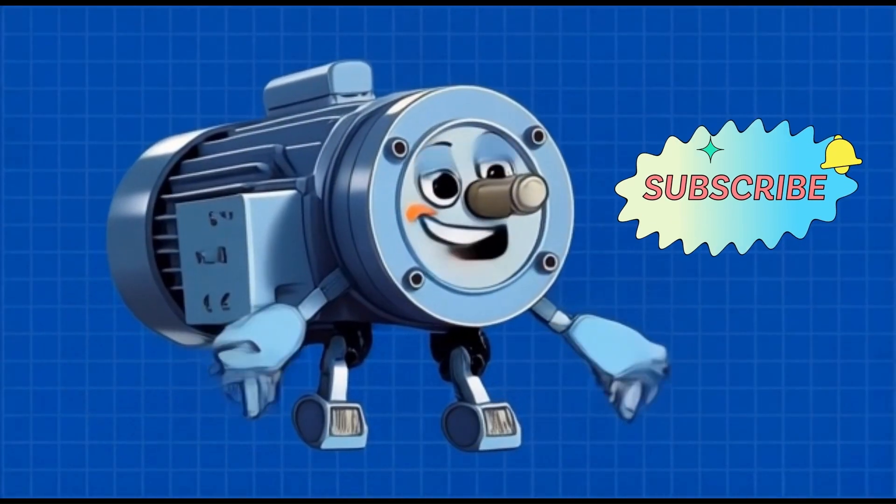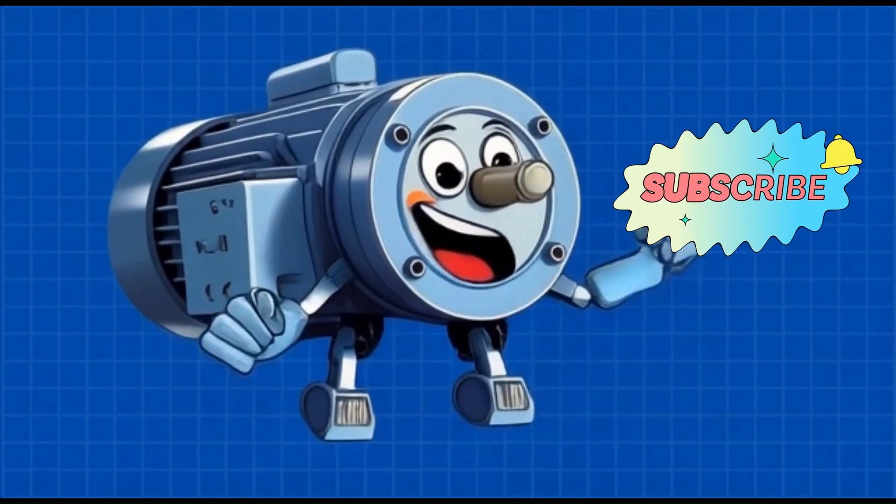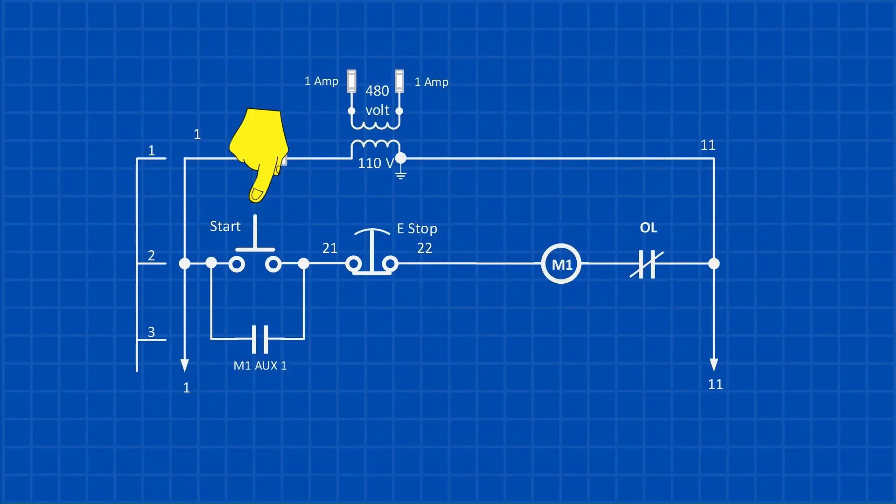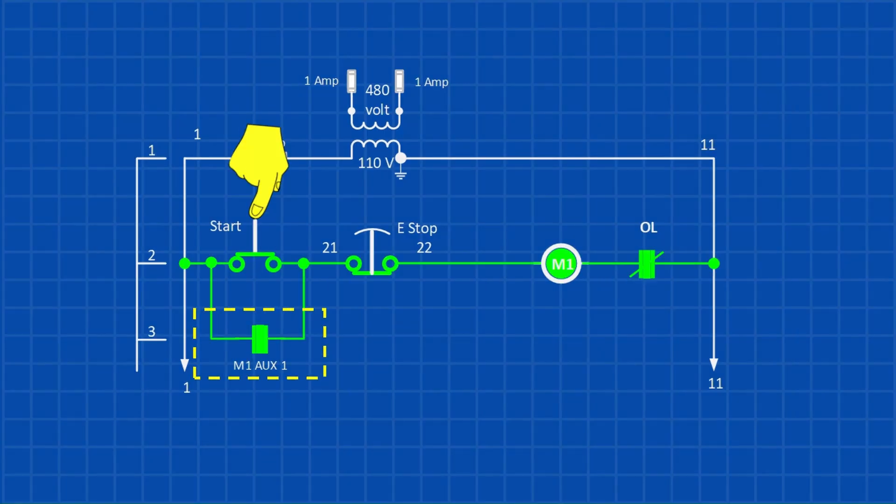If you haven't subscribed yet, go ahead and hit that subscribe button and give us a thumbs up. A motor starter control circuit uses what's known as a latching circuit. A latching circuit keeps the motor starter energized even after the initial start signal is removed. It works by using one of the motor starter's normally open auxiliary contacts, which is wired in parallel with the start button. When you press the start button, it energizes the M1 coil, closing the auxiliary contact. This contact then continues to supply power to the coil even after you release the start button. The motor starter coil stays energized, or latched, until you press a separate stop button, which is wired in series with the circuit.